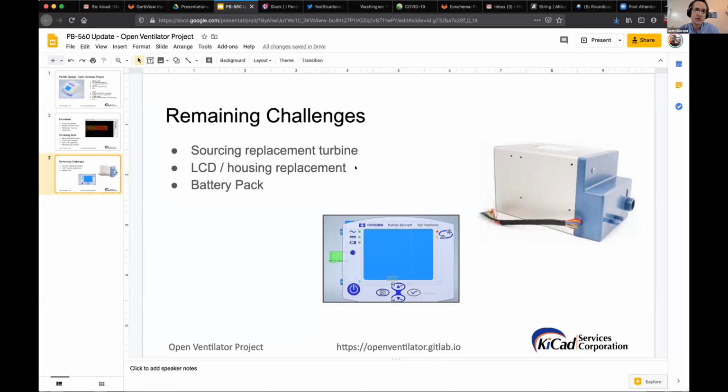And so any manufacturers that we are able to interact with that are able to help us with producing this, we are happy to provide electronic support and programming experience. We can design test jigs and get through the Medtronic certification. In case you haven't looked at the documents yet, the Medtronic file release pack not only includes the plans, but there are also full manufacturing testing procedures contained within that, and so we can verify to Medtronic specifications the functionality of the end devices.